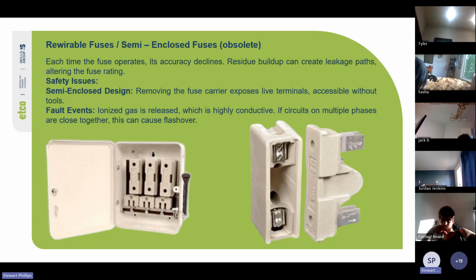So if you look at the base of a ceramic fuse holder, there's one pictured there. You can literally touch both sides, both live and dead, of the fuse base. The modern plug-in circuit breaker type bases, the plastic ones, at least have plastic covers, and you need screws to get to the conductors.